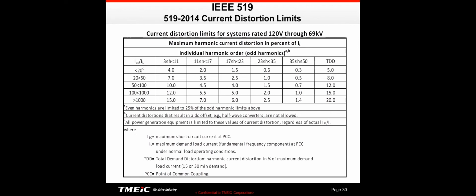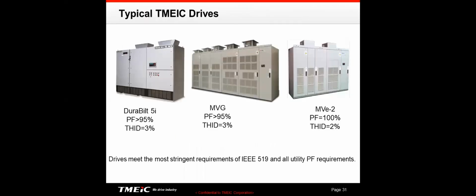And on medium voltage drives, it's very easy to get quality medium voltage drives that are under 5%, and you don't have to pay a premium for that. So on low voltage drives, we don't necessarily go to 5% because it's very, very difficult to get there. On medium voltage drives, it's not. It is just not difficult to get there. And so buy a good quality medium voltage drive. You should ask for a drive with not more than 5% total current distortion.